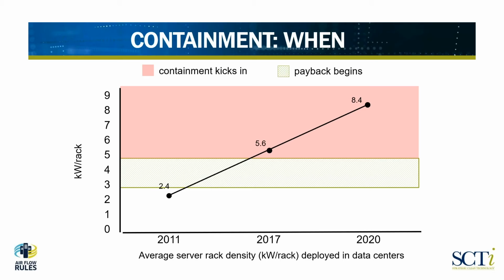And in 2020, the average was pushing up to 8.4. To your point, Cary, typically it's looked at as saying, well, if you're in a raised floor environment, once you start hitting that 5-6 kilowatt per rack heat load, you get to the point where you should seriously be considering containment, because it becomes more and more difficult to provide the proper inlet air to the IT equipment at that point.